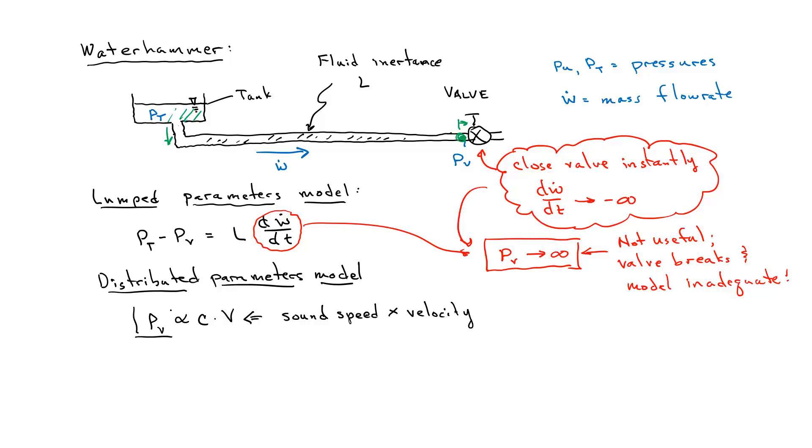Another important design parameter is how long or what the duration of this pressure is. Well, this pressure is going to stay high until the news that the pressure increased gets up to the tank, adjusts the velocity up at the tank, and works its way back down to the valve again.